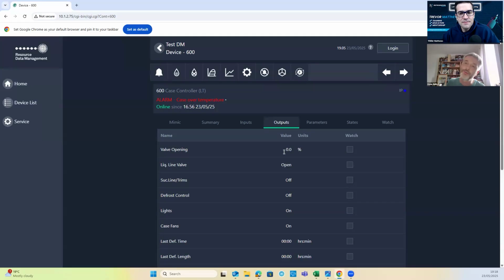One thing to note with RDM, if it's a mechanical valve with a solenoid, it is wired fail-safe. So on the back of your controller, it's wired to normally closed, as are the fans, right? So check your relay 1, your relay 2, wired normally closed. This is basically so if the controller blows up at some point, or somebody spikes it or whatever, you've got a little bit of a chance of keeping your food cold. And you're hoping then that somebody's noticed it's gone offline and they're going to do something about it. But that is how they guarantee that you've got a bit of cooling. So normally closed for fans and valve. On an electronic valve, the third terminal isn't connected because it's not a relay, it's a transistor. So you're normally open for electronic valve.